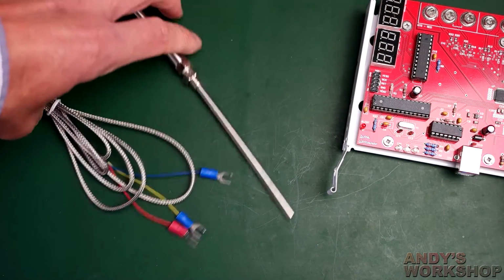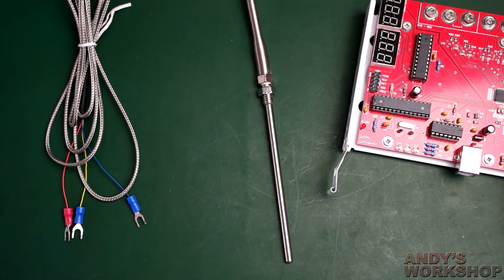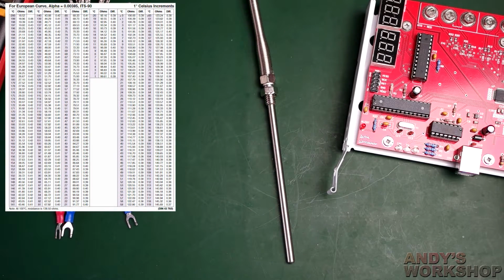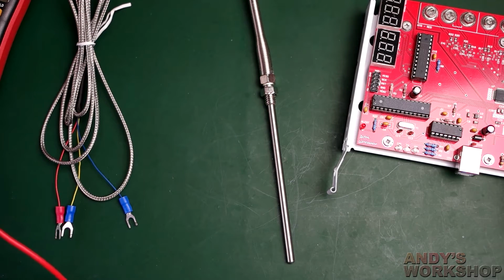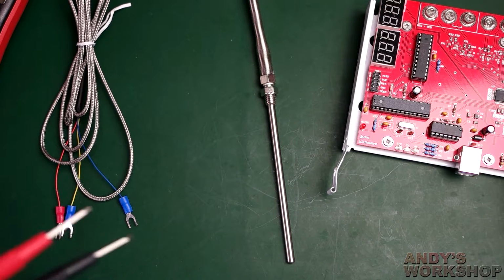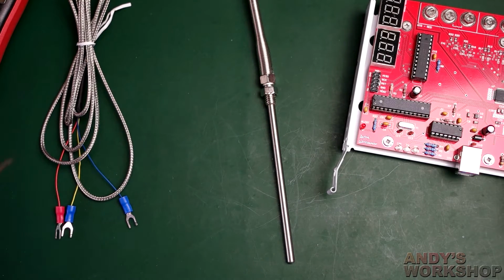It's easy to verify whether the RTD that you've got is actually any good, just simply by measuring the resistance. Now, there are online, and I will link this into the video in a little picture-in-picture window, a table of resistances to temperature. So you can just measure across the leads here and see whether the RTD is anywhere near what its nominal value should be, and whether it's going to need calibrating or not. So let's check out this one that I got from eBay.